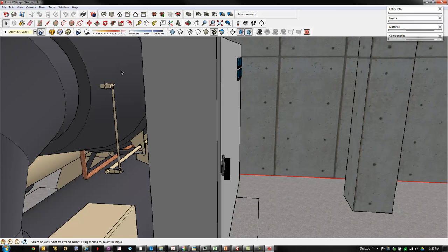The temptation is to think of those inlet guide vanes as throttling the refrigerant flow, in other words, making it harder for the refrigerant to enter the impeller and therefore reducing its capacity. And that's probably true a little bit, but what they really do is redirect the refrigerant into the impeller. They change the relative angle between the flow of the refrigerant into the impeller and the flow of refrigerant through the impeller, and that shifts its performance. So that's actually how they work. They modify the performance of the impeller by changing the flow path of the refrigerant.